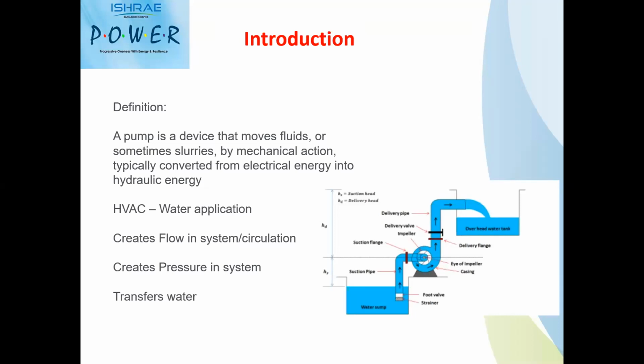A pump will have a driver, which will basically be a motor. In some specific applications, an engine will drive the pump. That electrical energy is converted into mechanical energy, which helps to move the fluid from one location to another, converting it into hydraulic energy. In HVAC terms, we can say it creates flow in our chilled water system. It creates pressure in the chilled water system, and it is used for transfer, like in a cooling tower application, where water is pumped from the condenser loop to the cooling tower and again back to the condenser loop. So basically, it creates flow in the system, creates pressure in the system, and transfers the water.